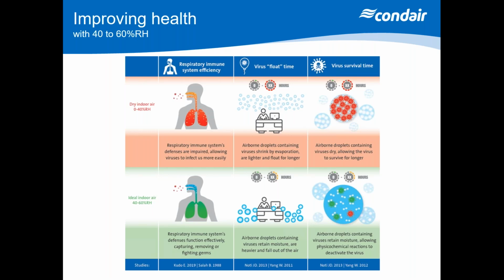Basically, if we're working in a dry atmosphere of less than 40%, we've got a protective mucous membrane in the back of our throat, which acts like a barrier to prevent these nasty airborne pathogens, like the coronavirus floating around in the airstream, from entering into our lungs. Now, if that mucous membrane dries out because of the drier atmosphere, it makes it less effective. So we need to raise our humidity to 40 to 60% to protect this mucous membrane when we're working in an office environment.